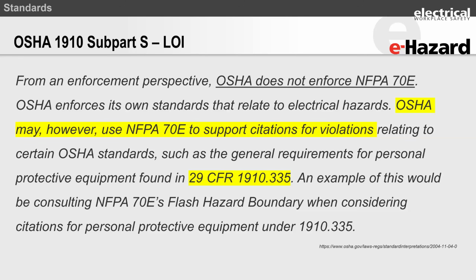Now, if you look at the arc flash hazard, none of the OSHA standards actually speak about establishing the arc flash boundary using IEEE 1584. IEEE 1584 is referenced within Appendix E of OSHA 1910.269. Okay, but if you look at subpart S, because you got the citation on subpart S, subpart S does not cover the establishment of the arc flash boundary. This is where you will need to go into NFPA 70E, and NFPA 70E offers you two options for identifying the arc flash hazard boundary, which is the NFPA 70E table method, that can be used, and that's in Article 130. Or you can use the engineering analysis method, which is in Annex D. Preferably Annex D7 is the one that's very common and used widely.